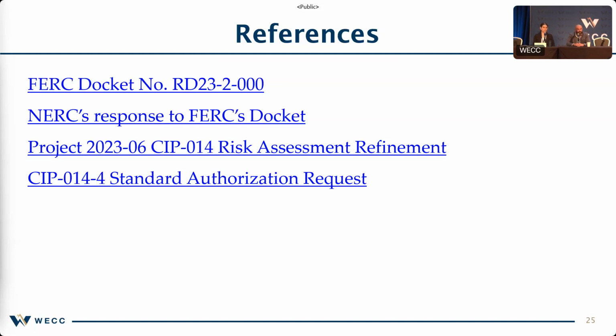I'm not a transmission planner, so I don't have a lot of developed reasoning for why line of sight and proximity is included there. I'm coming at it strictly as a physical security person, thinking about the threshold that would make a site critical, in what I'll call R4 through 6 right now since it's not version 4 yet. If you had two sites within that 2,000 meter bubble that didn't individually hit the threshold for CIP 14, but studied together they would, my guess is it's going to make them study together. And if, in combination, they meet that megawatt threshold, then they would both be CIP 14 sites.